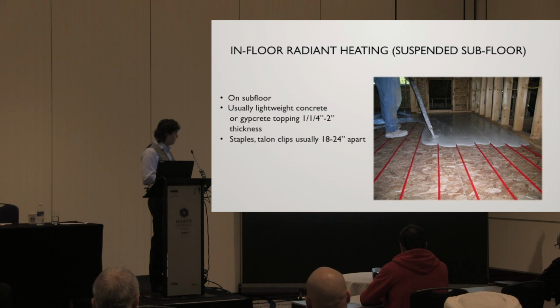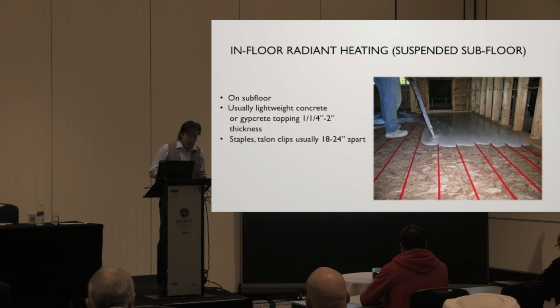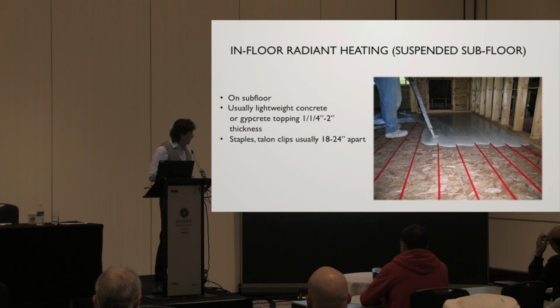Usually 18 to 24 inch spacing. In our hot water heating code, we say 18 to 24. Some inspectors say 18, you do it every 18 inches. It's kind of up to you in a sense. If that's tested with air, you might get some floating if you're too far apart. If you're 2 feet or beyond, you're going to get some floating there. So 18 to 24 seems to be the sweet spot.